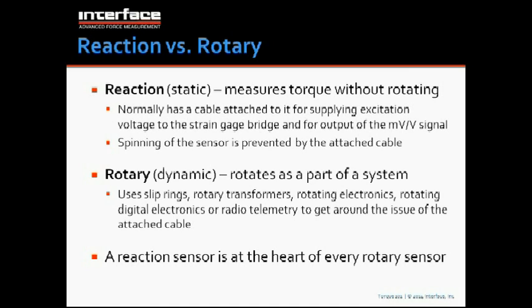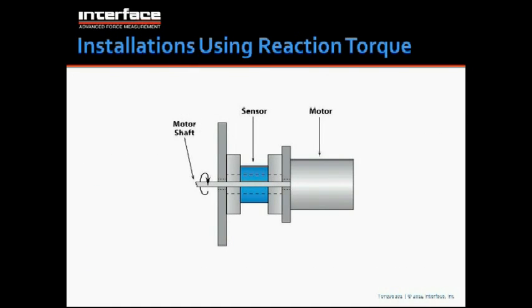And of course, in some applications, the sensor must spin. For example, if you're measuring the power of a motor and you want to measure it in line on the shaft, the sensor has to spin to make the measurement. But on the other hand, the sensor itself doesn't require that it spin to work. This is an example of a reaction sensor.